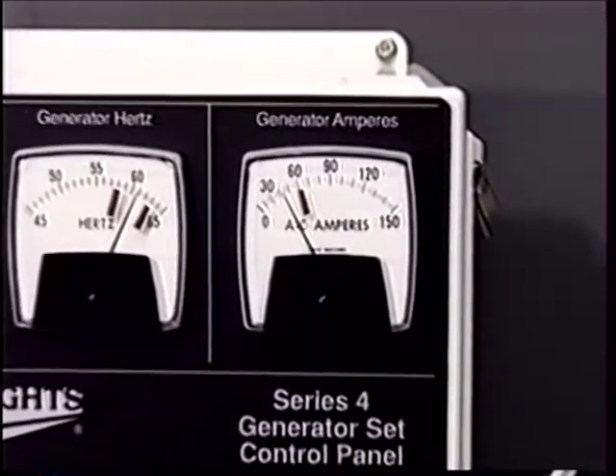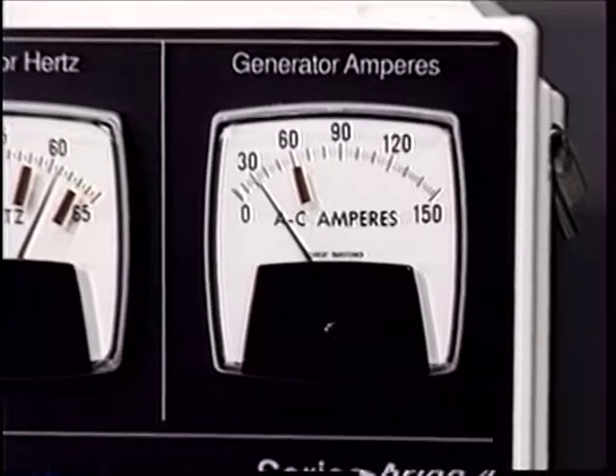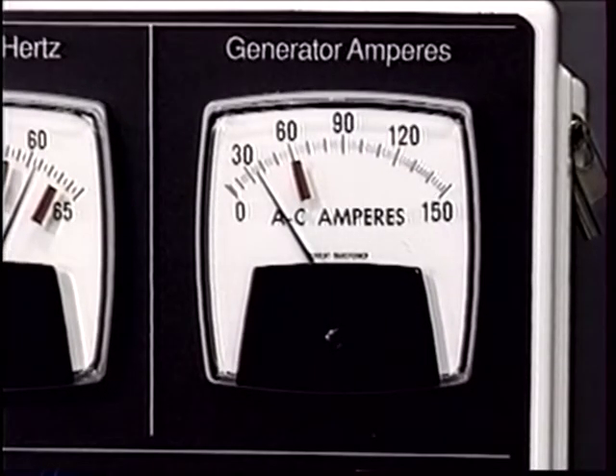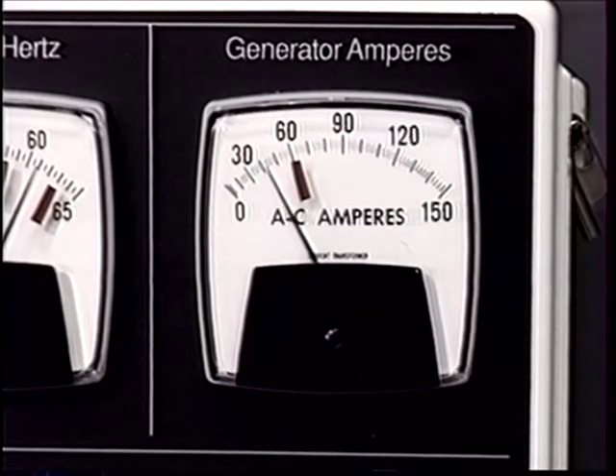Check your amp meter and familiarize yourself with the load levels of your system. Under normal operating conditions, a continuous load should not exceed 75% of the generator's output. This does not account for intermittent high loads and/or surges that may occur.